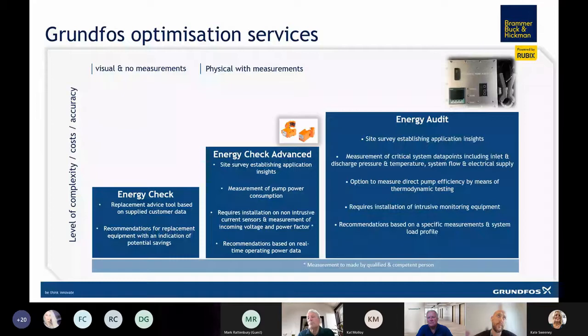When we're looking at a pump audit, we'll also make recommendations in regards to pipe layouts and pipe systems. We see a lot of installs where it's not quite the right connections into the pipe, or the pipe is reducing down way too small from quite a substantial size pipe into the pump. So we will also offer recommendations on what the best option is when looking at pipe layouts as well.